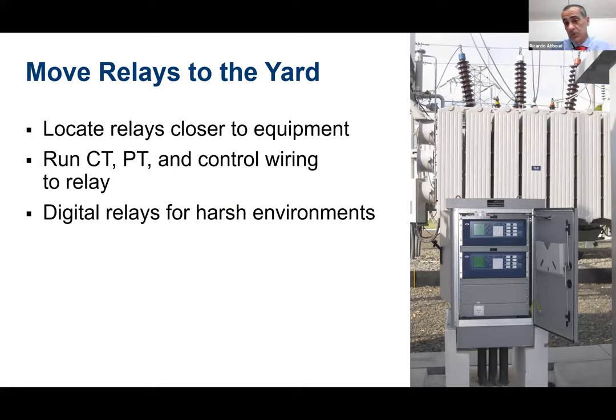Another approach to eliminate copper cables, or to reduce them, I cannot eliminate, but we can reduce the copper cables in the substation, is to move the relays to the switch yard. That means, instead of installing the relays in a control room, I'm going to install the relays in the switch yard in an outdoor cabinet, like in this picture here, in this figure. Okay. So what I need is a short run of copper cables to connect the primary devices to these relays. They are really close. So it's a very short, it's not a long copper cable.